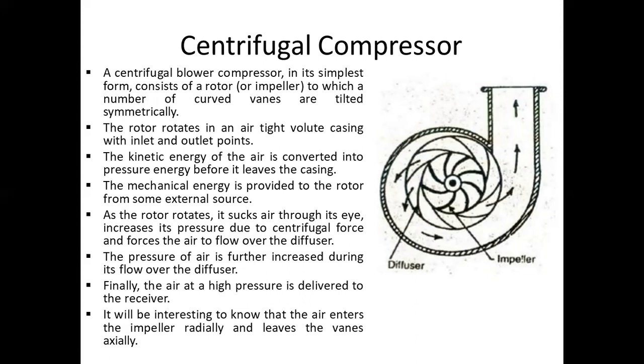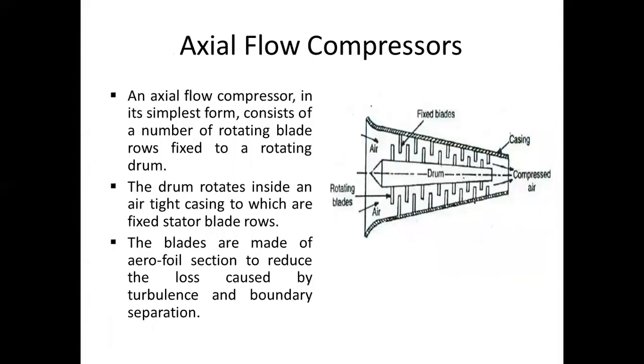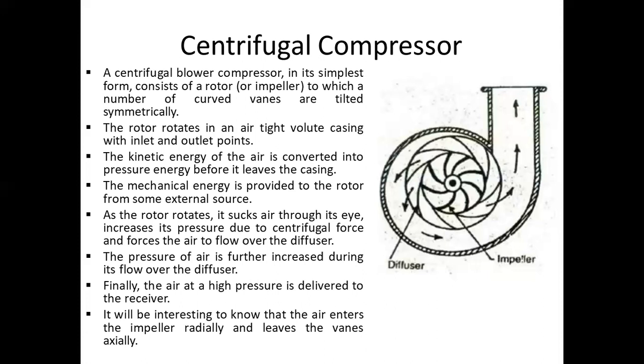It will be interesting to know that the air enters the impeller radially and leaves the vanes axially. The curved vanes as well as the diffuser are so designed that the air enters and leaves their tips tangentially without shock. Their surface is made very smooth in order to minimize the frictional losses. The work done by a centrifugal compressor may be found out either by the velocity triangles or otherwise.